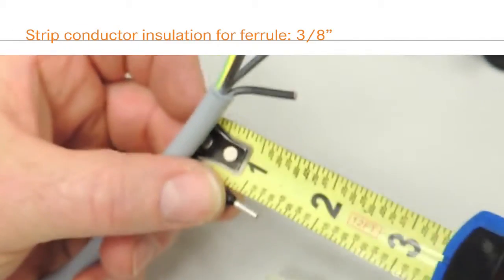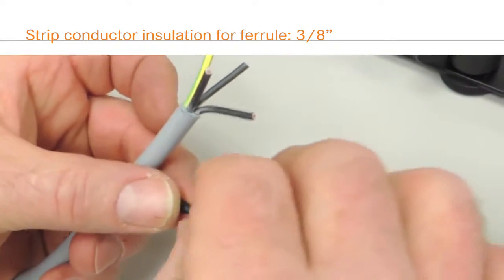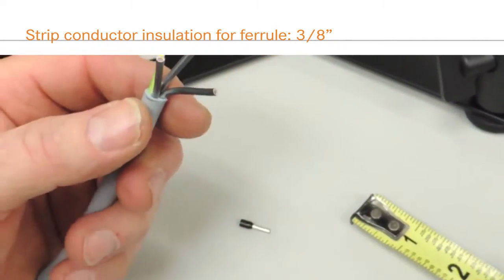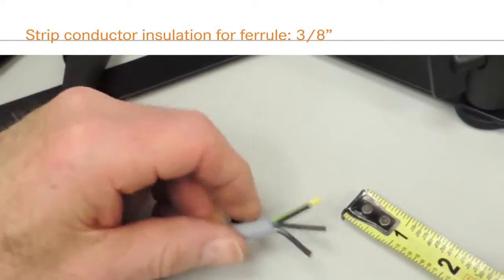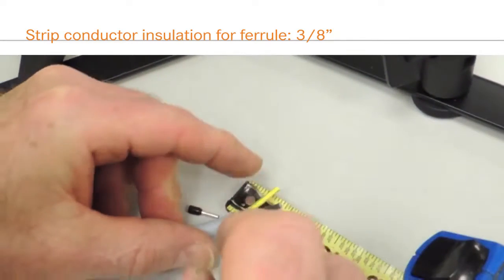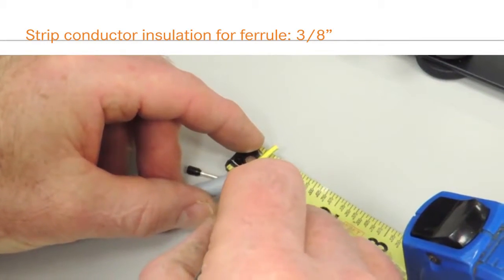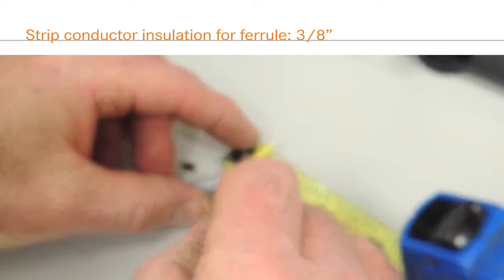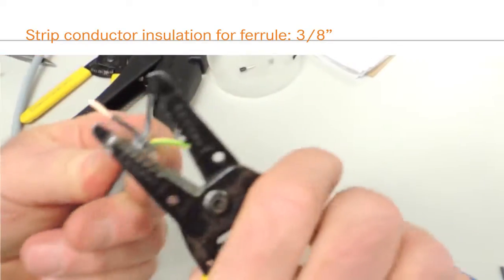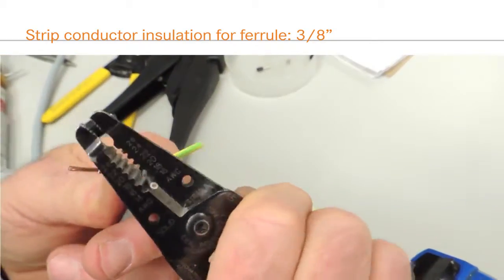Next, the individual conductors need to be stripped to accommodate the wire ferrule. Measure the length of the ferrule to determine how much of the insulation to strip. Three-eighths of an inch is a common stripping length for contact termination. After marking the conductors, use a wire stripper to remove the insulation.